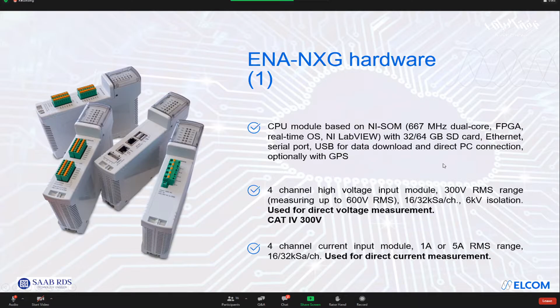Then for sure, we have the direct current input module. So it can measure either 1 or 5 amps, which are the typical outputs from the substation CTs. Usually you have on the substation, you have the current, which is measured by the current transformers. And these current transformers are either using 1 amp output or 5 amp output. So our current module can either take 1 amp or 5 amp as a current input.